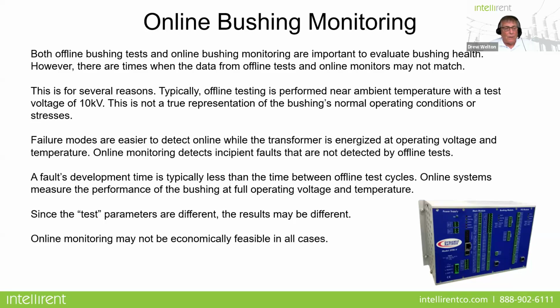Now, online monitoring may not always be economically feasible in all cases. You talk to customers, and they say, "Hey, I've got 480 transformers out there. I can't put a monitoring system on them." Well, then you better make sure your maintenance testing is well defined. If you take a guy that sells transformer test equipment and a guy that sells monitoring systems, they'll have a 2 hour argument and a Jerry Springer fist fight eventually. But for most cases, both are very appropriate.